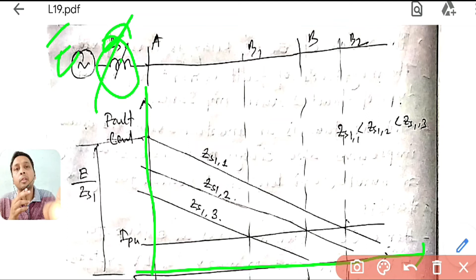Suppose you have set for a particular case where you know that your source impedance is ZS2. I have set with ZS2 so that my IPU reaches up to this much. This is my IPU level, suppose 10 ampere. So 10 ampere will be reaching. I want to protect this feeder from A to B. So up to this much, if there is any fault here, because ZS is this much, the fault current will be 10 ampere.